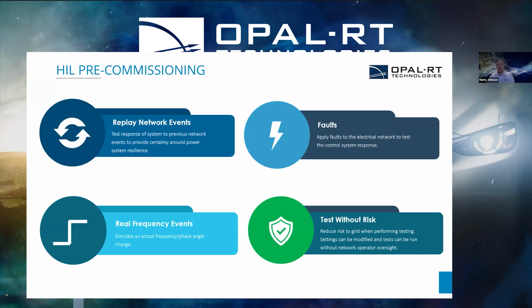And of course, on site, typically how we do this is something called continuous monitoring. We'd wait for a fault to happen on the network, and then go back afterwards and test whether we've complied or not. We can also do real frequency events. Because we have the power amplifier there, we can effectively change the grid frequency to make sure that the power quality meter is actually measuring the frequency as we expect. We'll talk a bit more on this one later, about why that's important.